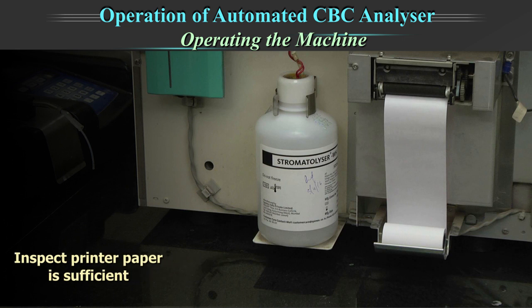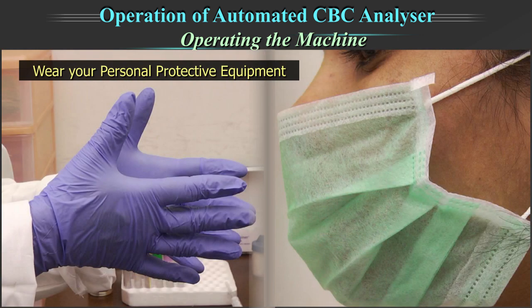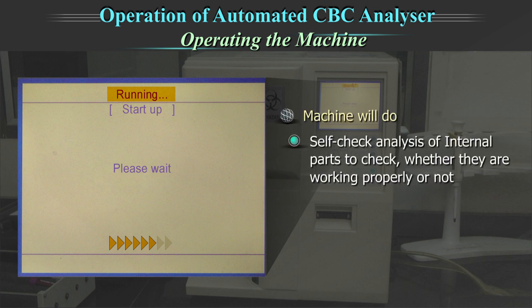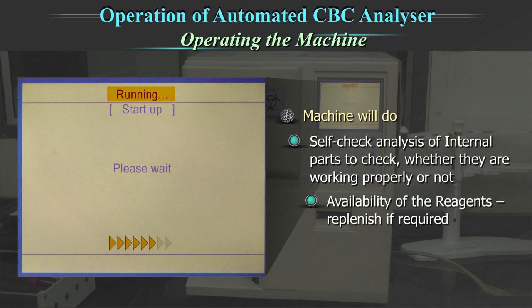Inspect if the printer paper is sufficient for the day's print. Wear your protective equipment. Standard precautions are to be exercised at all times while handling samples, equipment, sampling and maintenance. Switch on the machine. The start-up process begins and usually takes 4–5 minutes. During start-up, the machine will do a self-check analysis of internal parts to check whether they are working properly, check availability of the reagents, replenish if required, and perform any scheduled maintenance.